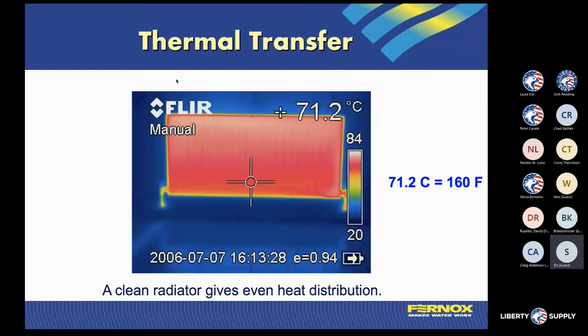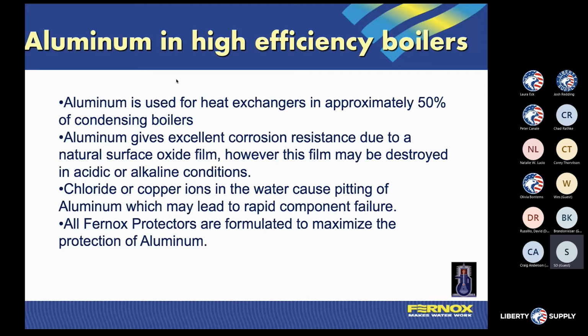So we're getting better temperature out of that system. We may not still be getting complete full temperature based upon set point, but we're going to get a lot better than that 93 degrees we started with. If we have an aluminum boiler heat exchanger or aluminum products in your system, they are even more sensitive to water quality. If you look at your manufacturer's installation guides, they're going to talk about pH levels. They're going to talk about how oxidation and corrosion from the likes of limescale are really going to be a factor. And again, this is where you may not be able to have a system last very long or get warranty if it does prematurely fail.